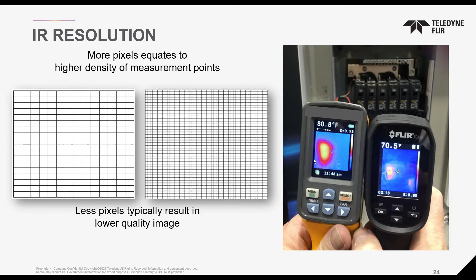So here's a look in a little more detail. Here's a series of motor banks, and on one of these motors we have a spliced wire. We'll look at this in different pixel counts. With a small pixel count, this is one pixel—this blue box is one pixel, and it takes the temperature of what's inside of it. So we're getting some of this green, some of this blue, averaged in with the white and red.